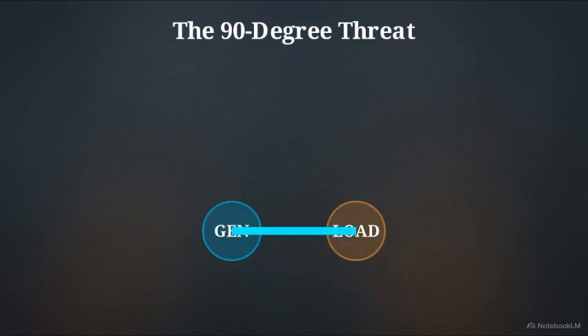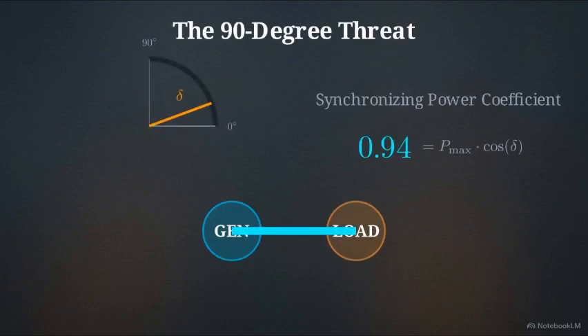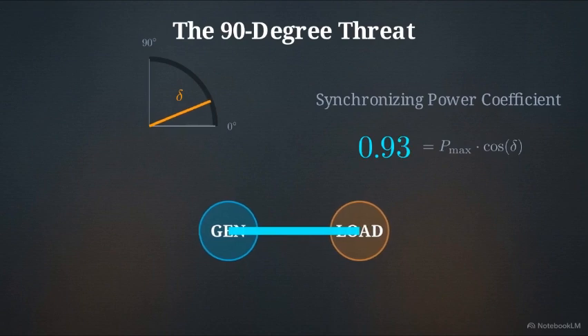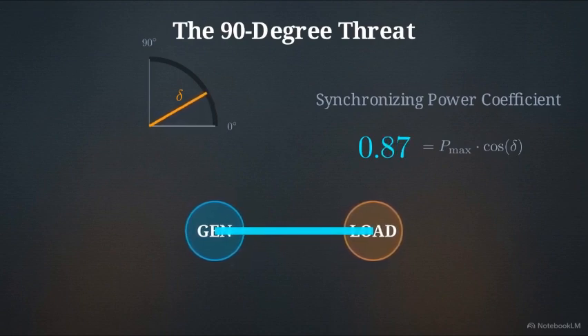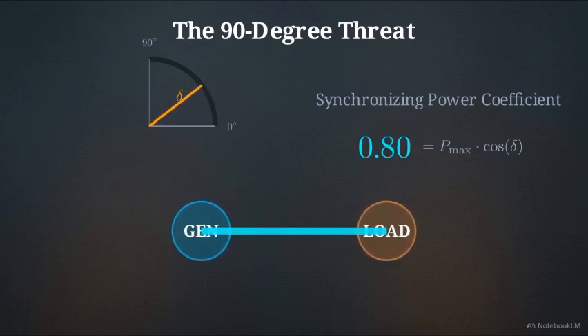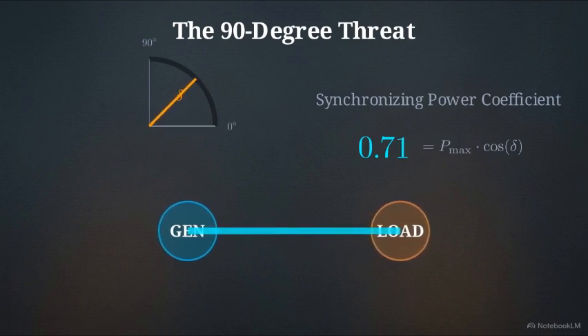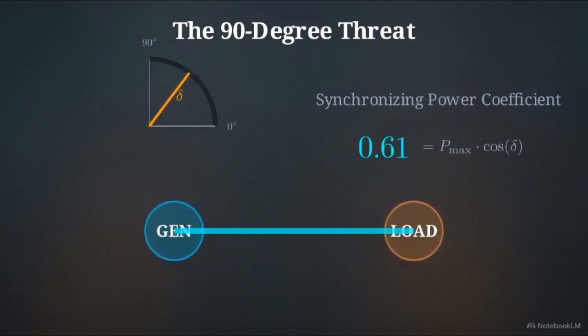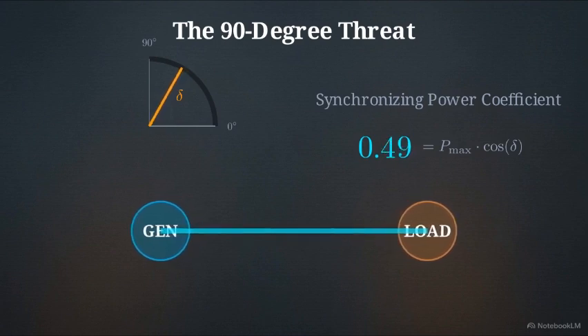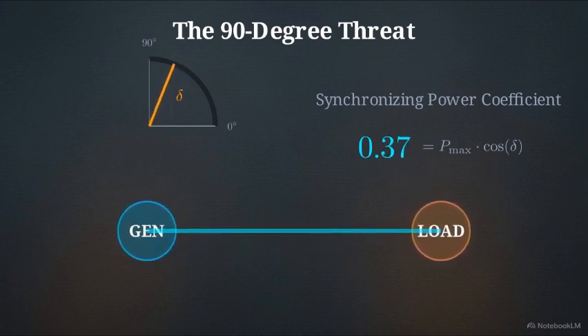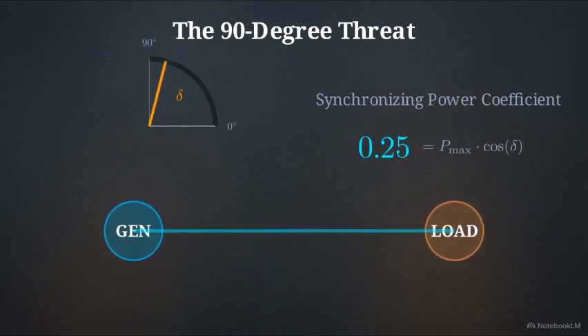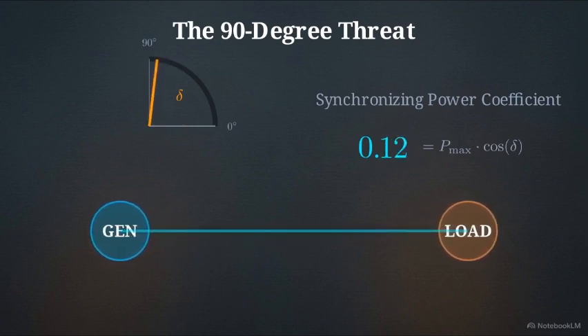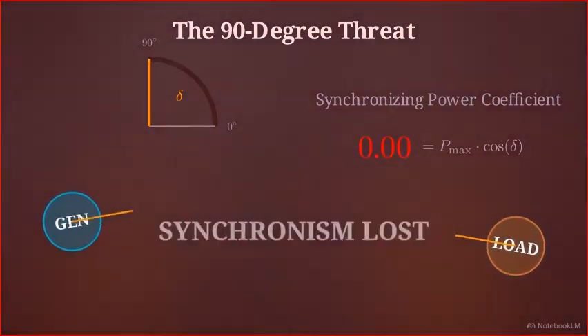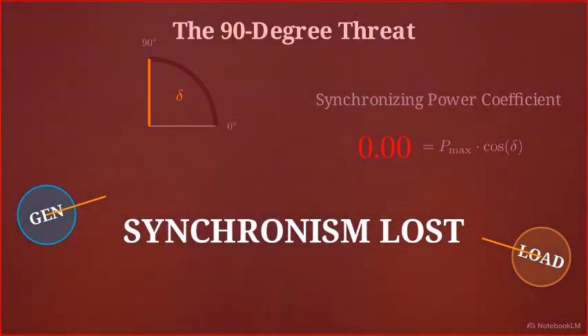This diagram shows a crucial metric for the grid, known as the synchronizing power coefficient. It determines the system's ability to stay locked together. Notice that as the stability angle, delta, widens, this critical coefficient directly drops. The further the power travels, the weaker the system's grip becomes. Watch what happens to the connection on screen as the angle hits exactly 90 degrees. The coefficient flatlines. At this exact mathematical limit, the system crosses its steady-state boundary, permanently loses synchronism, and collapses.